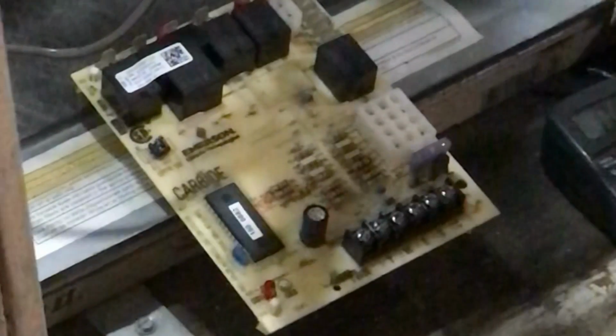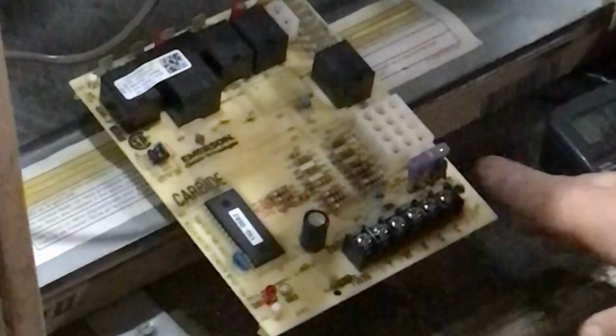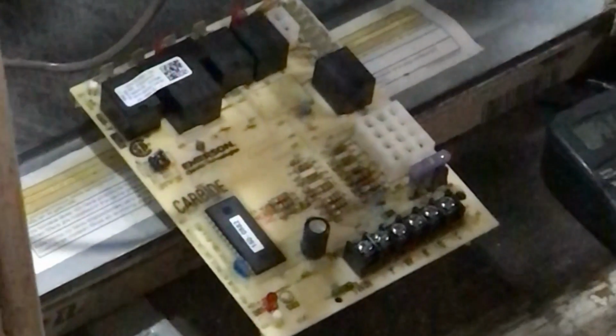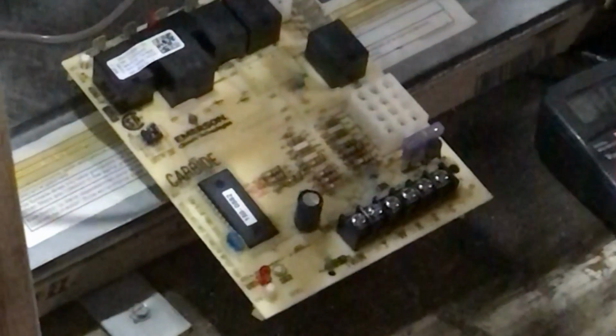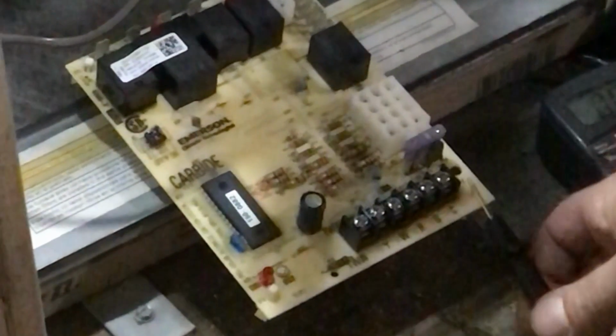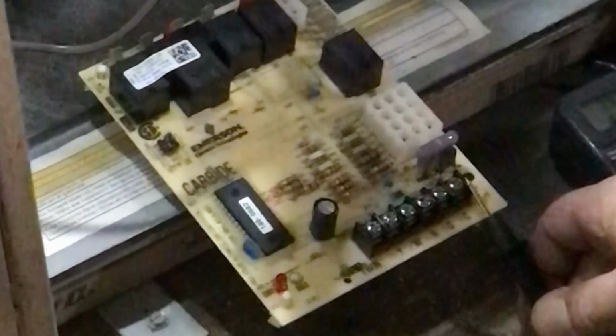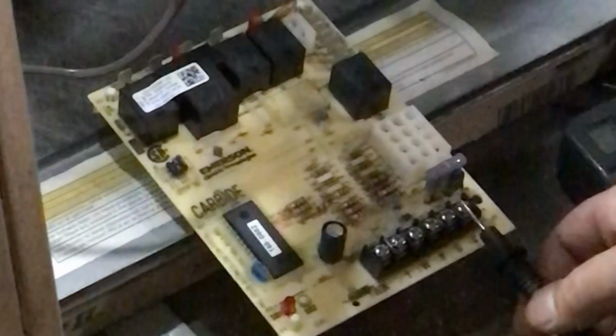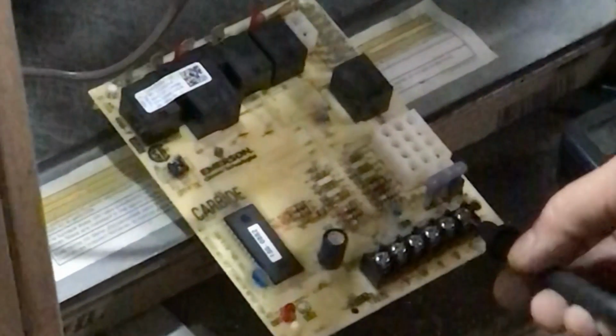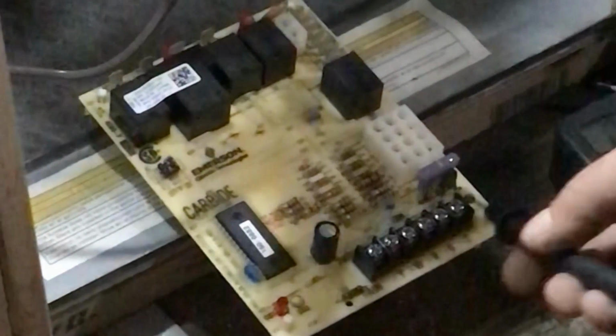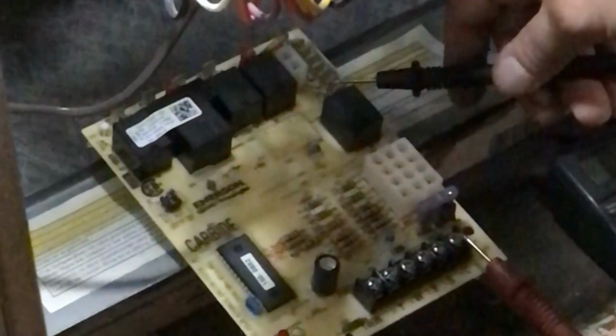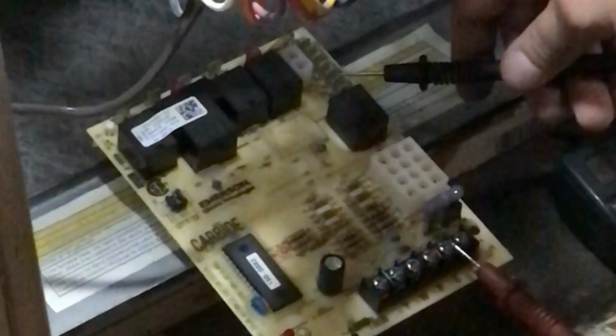It's just another power wire. A lot of times this won't be in use. When it is in use, the purpose of it is if you have a thermostat that requires 24 volts to operate. For example, a thermostat that does not use batteries. So that's another check you want to do if you're not getting your 24. You want to see if you're getting 24 out of this common. If you happen to have that type of thermostat, it will not work if you don't get 24 volts coming out of this terminal. So just like everything else, you want to go to this terminal, to a neutral, or a known ground. And that's the same way you would test your fan. See if you were getting power to your contactor.